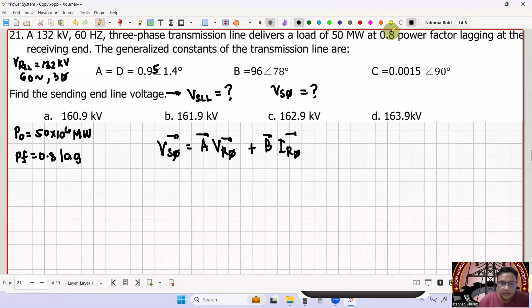Pero bago natin makuha yung VSLL, kunin muna natin yung VS per phase gamit ang generalized parameters. So VS per phase ay equal to A times VR per phase plus B times IR per phase. Kaya ito ay equal to A, which is 0.95 bar angle 1.4, multiplied by VR per phase. Meron tayong line-to-line na binigay, kaya gagawin natin per phase: 132 kilo over square root of 3 bar angle 0, plus B, which is 96 bar angle 78, multiplied by IR per phase.